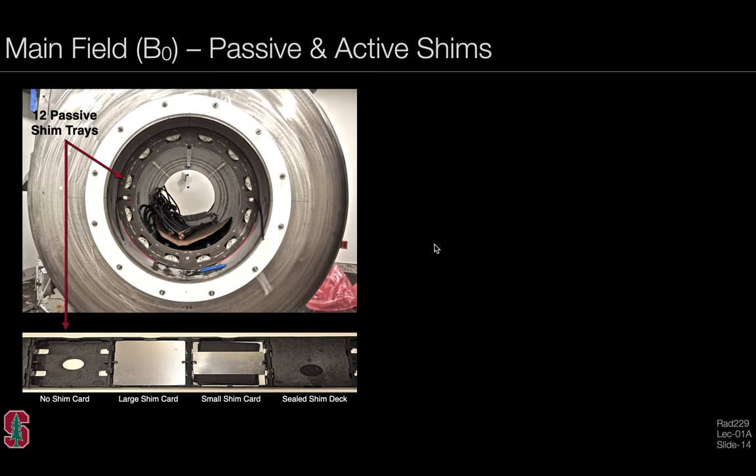The main B0 field, when delivered, is quite homogeneous but not perfect. It can become less homogeneous as a function of time as the system environment changes, and when subjects or objects are added to the scan environment. We'll discuss briefly the concepts of passive and active shimming.